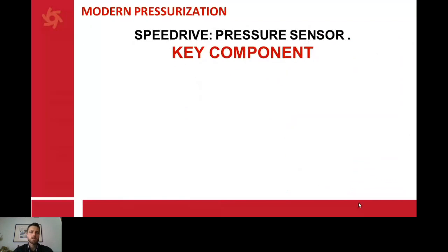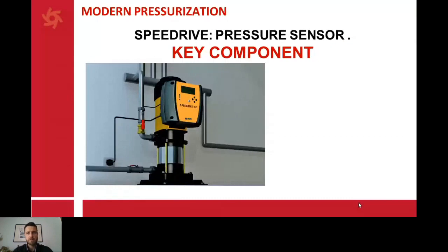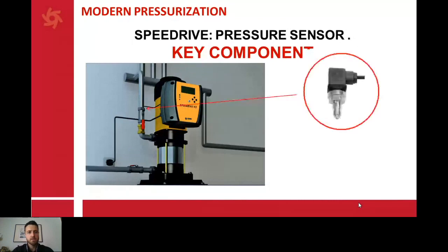But which is the key component also in the booster set? This is the pressure sensor. The pressure sensor is in charge of telling the pressure in all the moments to the SPEEDRIVE. So this makes the speed of the pump go up or down, so we can always adapt to the demand that we have on the system. If the system requires 4 cubic meter or 2 cubic meter or 8 cubic meter, we always will have the same pressure, thanks to this key component that is reading the pressure all the time.